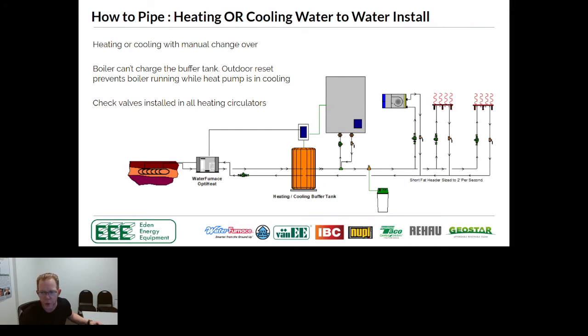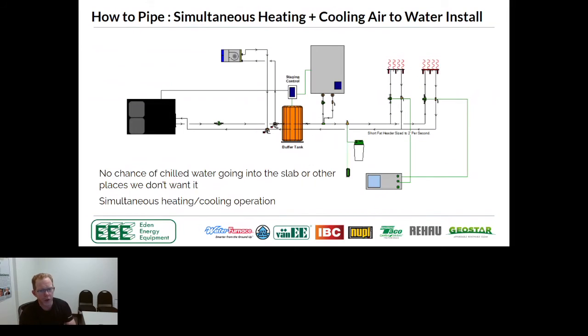If you're expecting the homeowner to turn the thermostat to the off position, hopefully somebody listening to me is chuckling right now, realizing the homeowner's not going to do that. So you could have this air handler cooling. This could still be calling for heating, and it could in fact be pumping chilled water through the slab, and they could call you and say, hey, why is my carpet wet? The radiant floor has got chilled water in it. So not trying to scare anybody, just trying to make people think outside the box as to what we would do. Here's another way that you can do it.